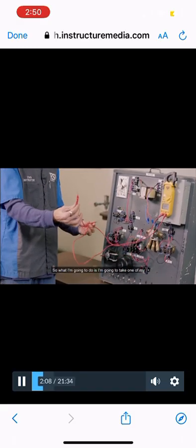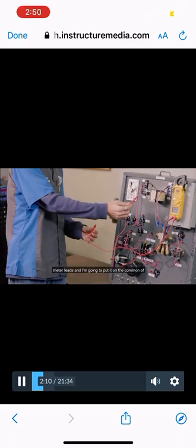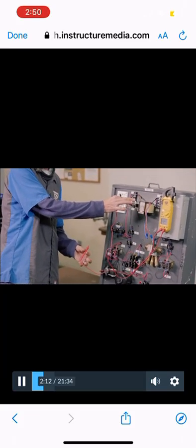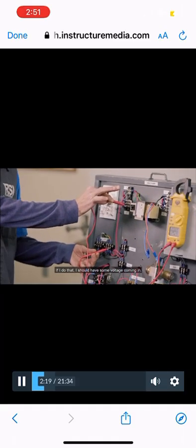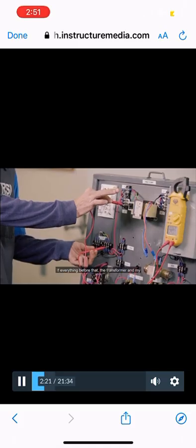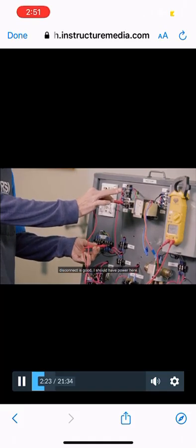So what I'm going to do is take one of my meter leads and put it on the common of the transformer, okay? And then I'm going to take my other meter lead and put it on the red terminal right here, okay? If I do that, I should have some voltage coming in. If everything before that, the transformer and my disconnect, is good, I should have power here. So I'm going to look, and I do.